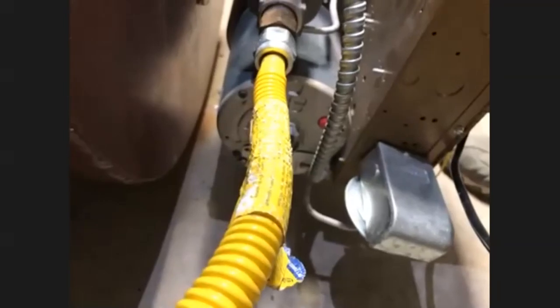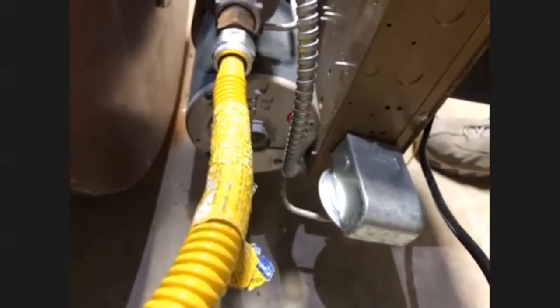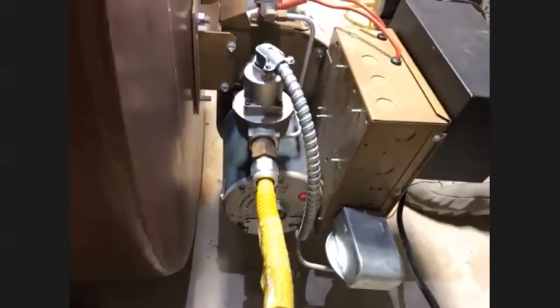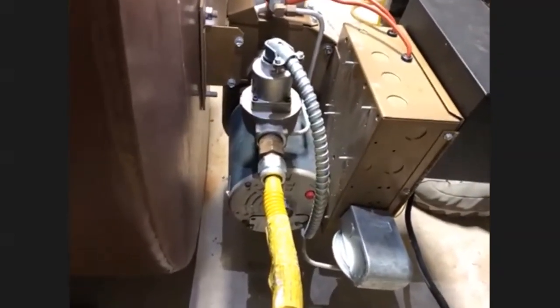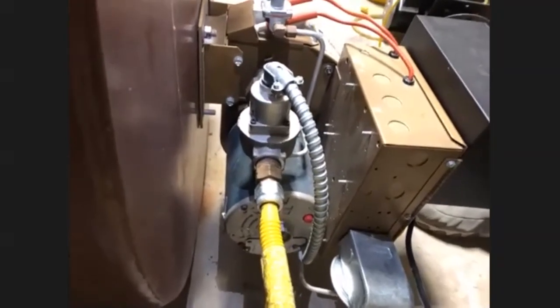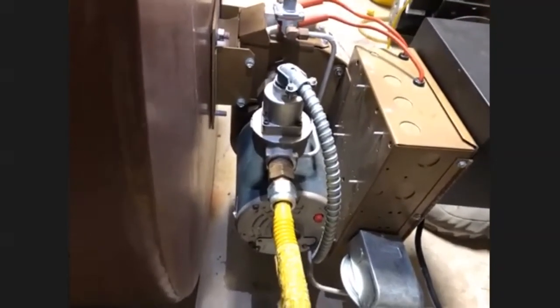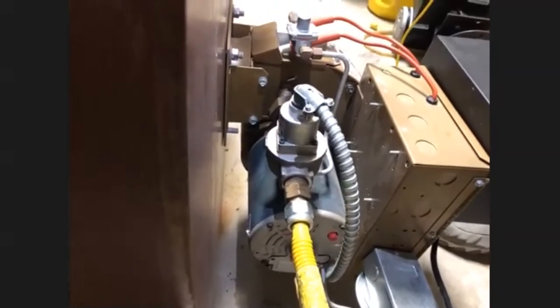So you want to verify that there is nothing inside this air tube. You may need to loosen it up. There are nuts and fittings on it. Loosen that up. You can take it out. It comes out of this housing, blow through it, and verify that it's nice and clean. If there's anything else inside there, like spider webs or dirt, I've even encountered water inside those. Any obstruction in there will prevent that from operating properly, and that will shut the blower down.